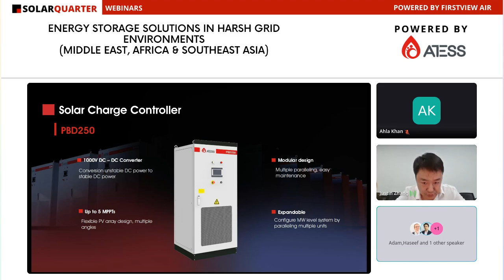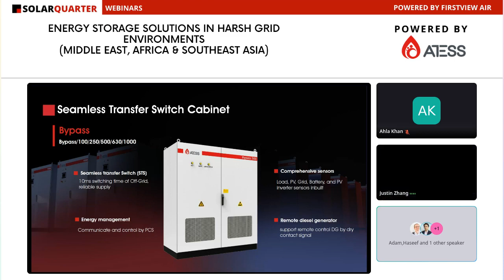Another associate of our PCS is this seamless transfer switch cabinet. As I mentioned before, we need to do the seamless transfer between on-grid and off-grid. That means we can have very stable power all the time, 24 hours, 7 days. Our bypass transfer time will be like 10 milliseconds, so even in your own factory or office, you don't even feel any blackout, because all the transfer is seamless. All the communication and management comes from the PCS. The PCS will communicate and control the bypass to do the seamless transfer between the grid, diesel generator, or even from the battery or the PV panels.